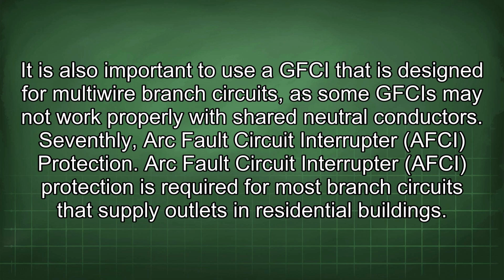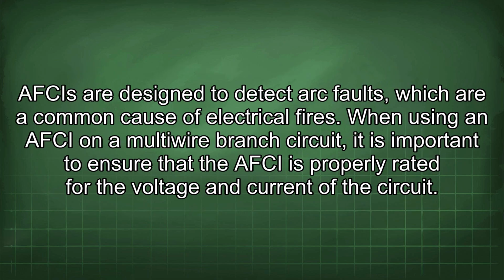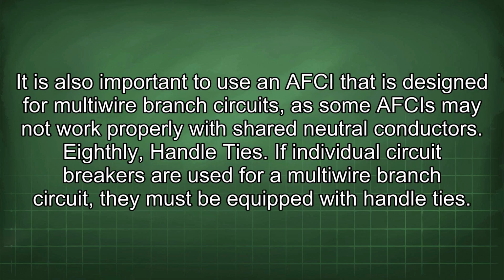Seventhly, arc fault circuit interrupter (AFCI) protection. AFCI protection is required for most branch circuits that supply outlets in residential buildings. AFCIs are designed to detect arc faults, which are a common cause of electrical fires. When using an AFCI on a multi-wire branch circuit, it is important to ensure that the AFCI is properly rated for the voltage and current of the circuit. It is also important to use an AFCI that is designed for multi-wire branch circuits, as some AFCIs may not work properly with shared neutral conductors.